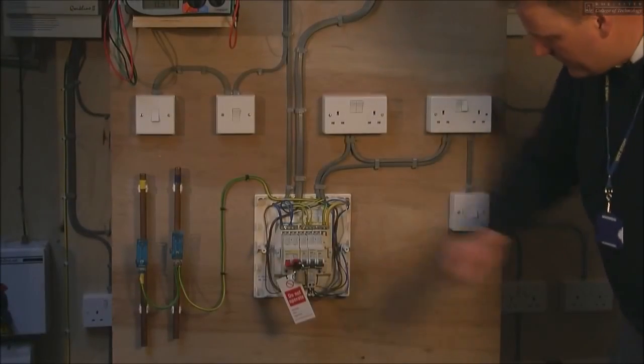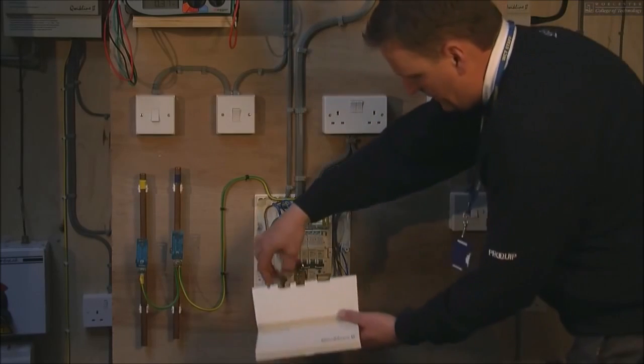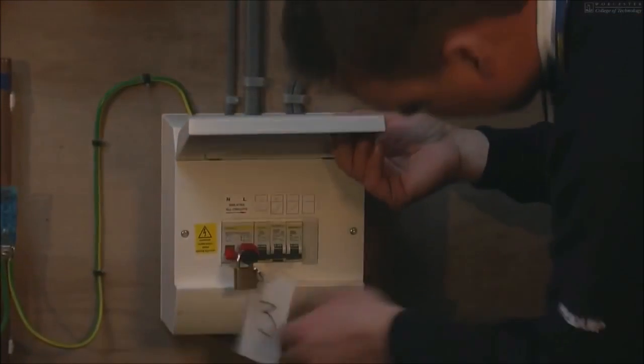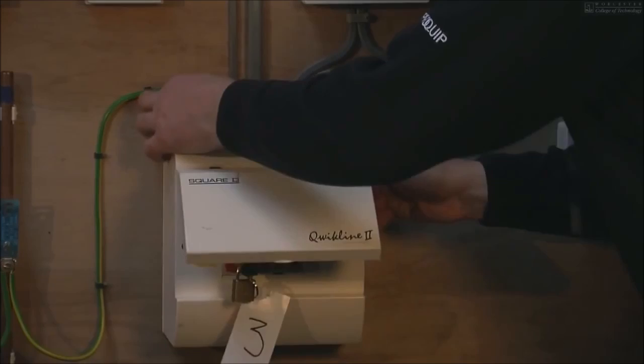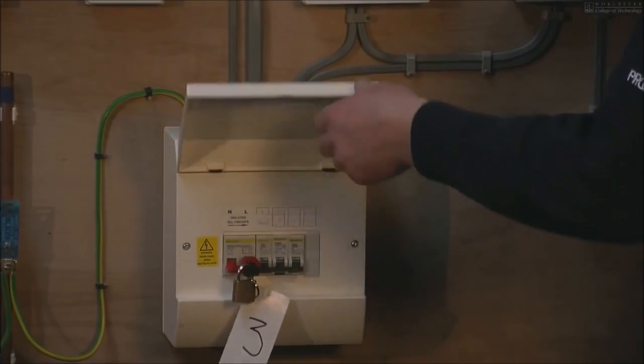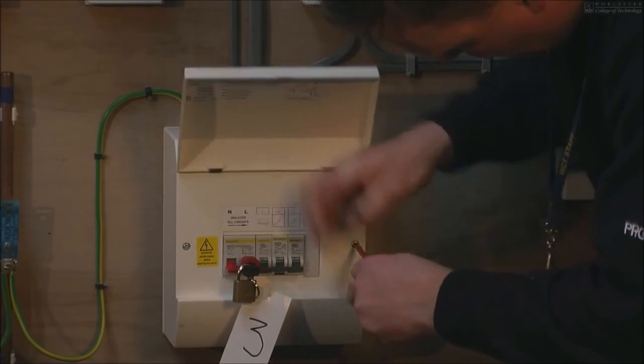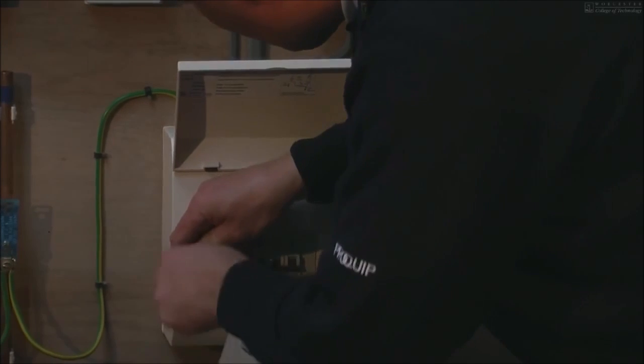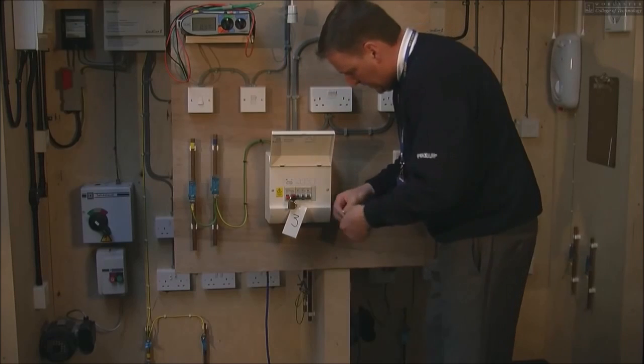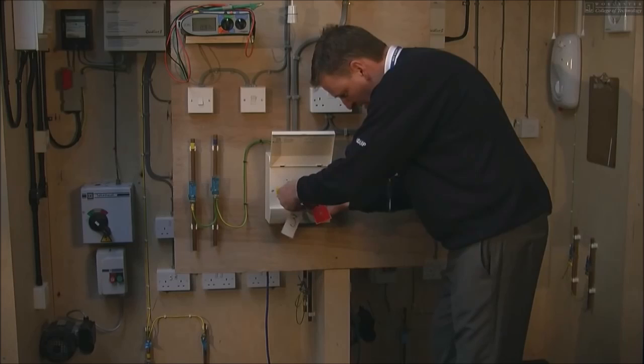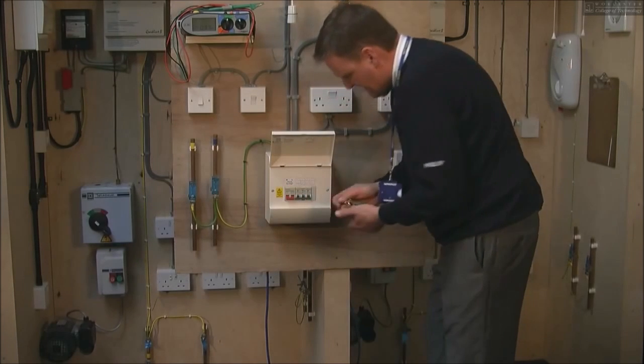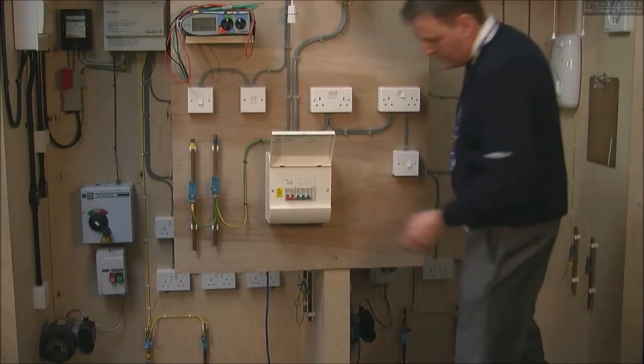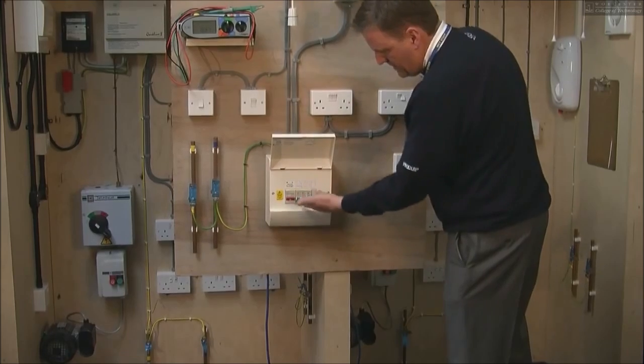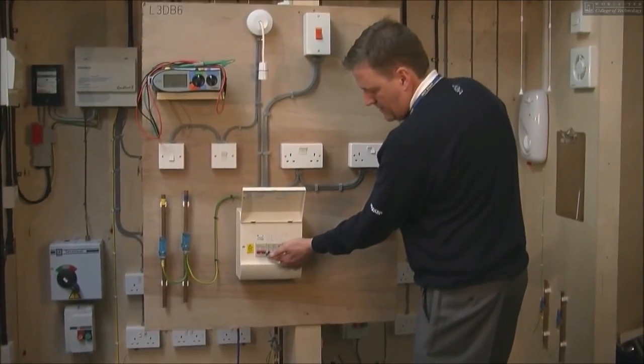Having reconnected all the cables and ensured that all the conductors are tight, we can now put the fuse board cover back on, like so. We then use a screwdriver to tighten the screws. We then take our key that's been in our pocket all along. We then begin to re-energise the circuits. So firstly the main switch. First circuit we're going to test is the cooker circuit, so we energise the cooker circuit first.